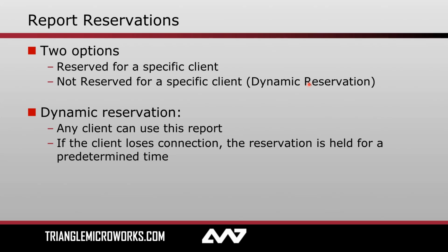It's a little bit of a misnomer, but it uses the term dynamic reservation in this case. The reason we still call it a reservation is because we still do get the benefit of the buffered reports. So effectively how this works is, let's say that I have chosen to have no reservations. All my report control blocks are available to anyone. And then I, as a client, come in and grab one of those report control blocks. Any changes that have occurred that are stored in the buffer before I connected will be passed up to me. And then some short time later, there's a communications interrupt and I disconnect.